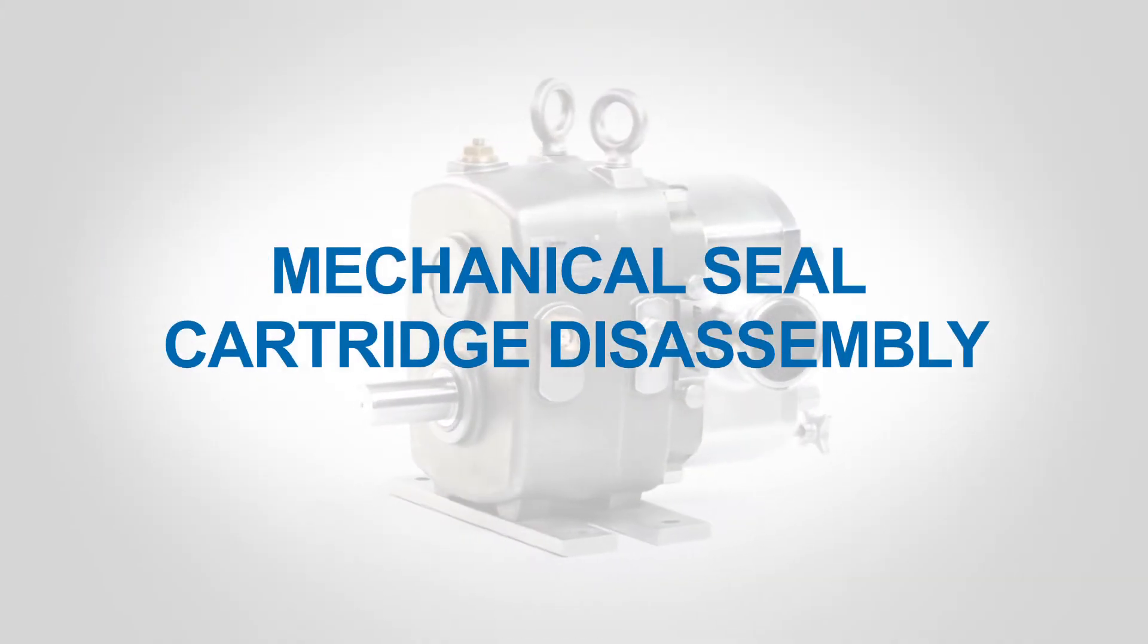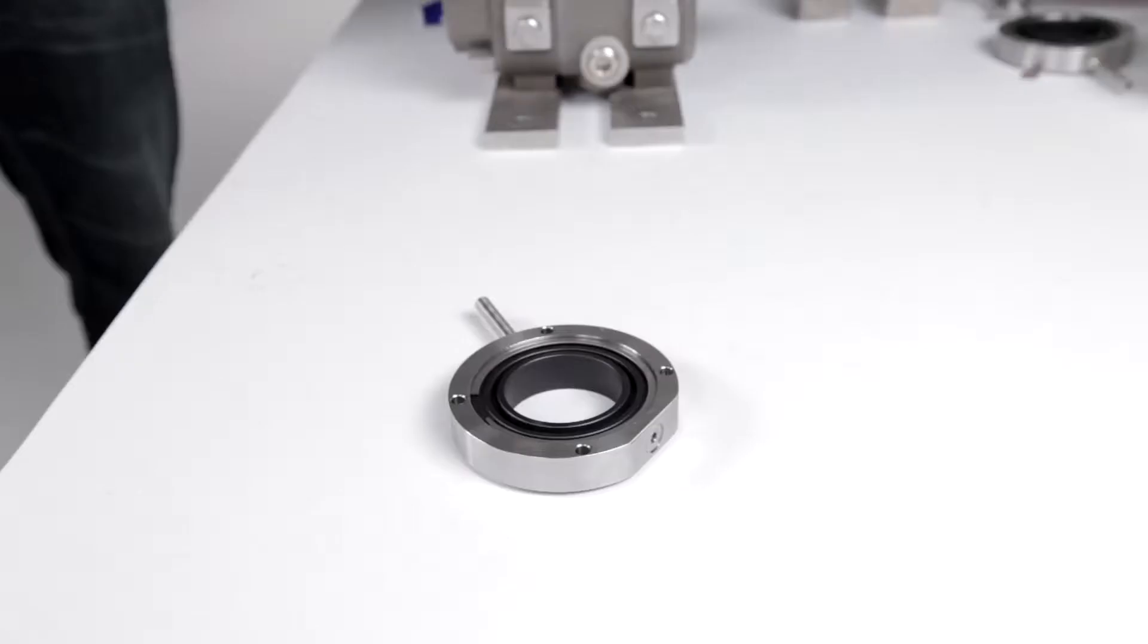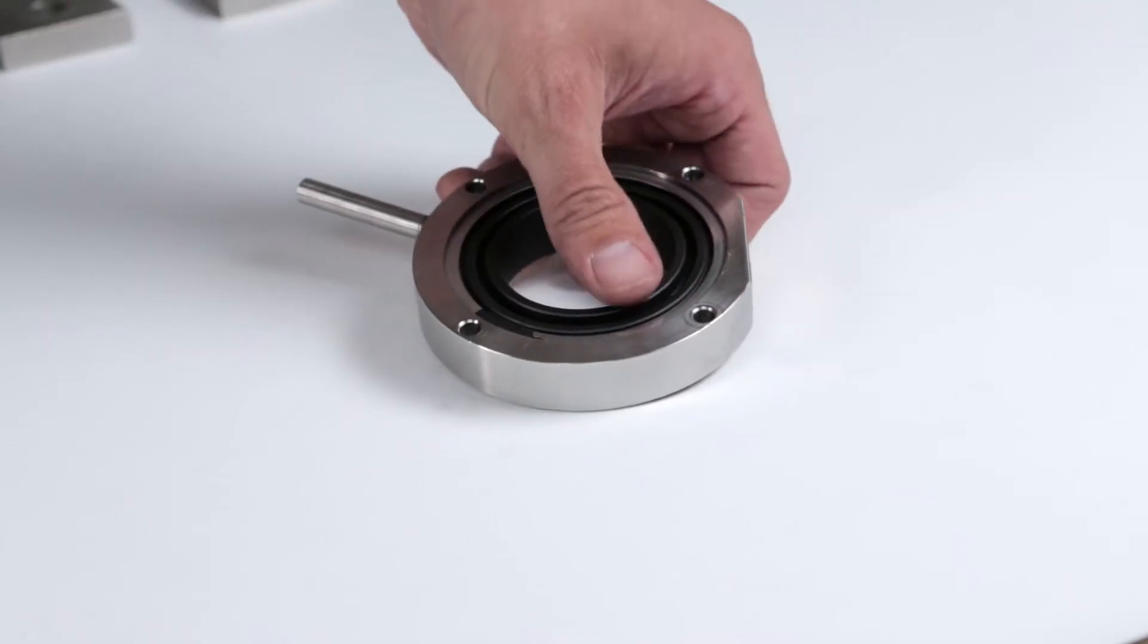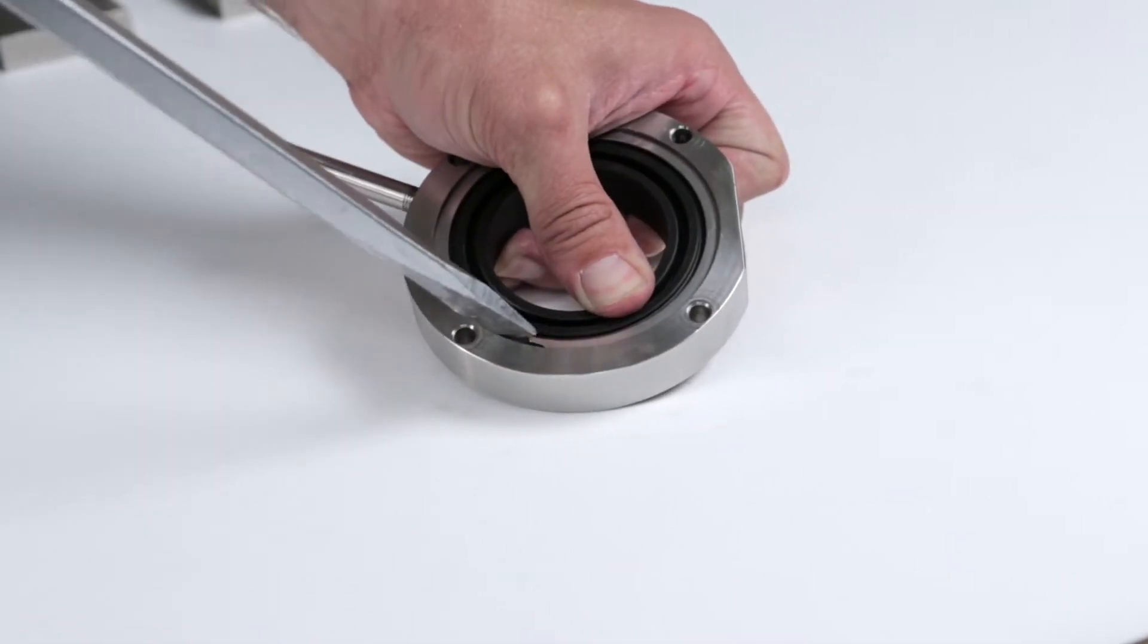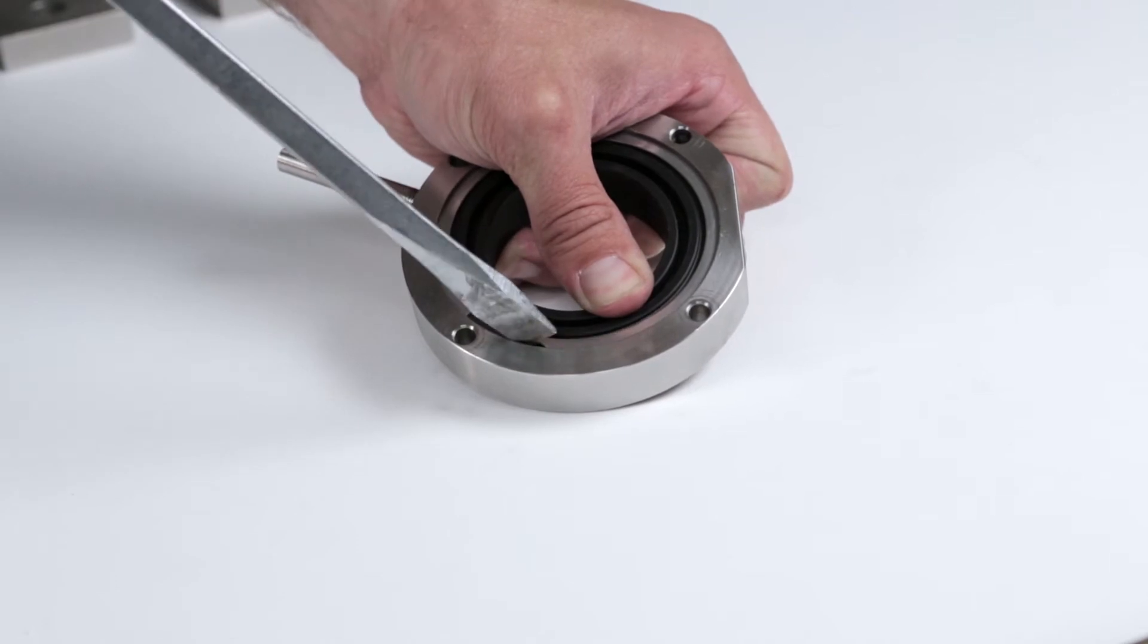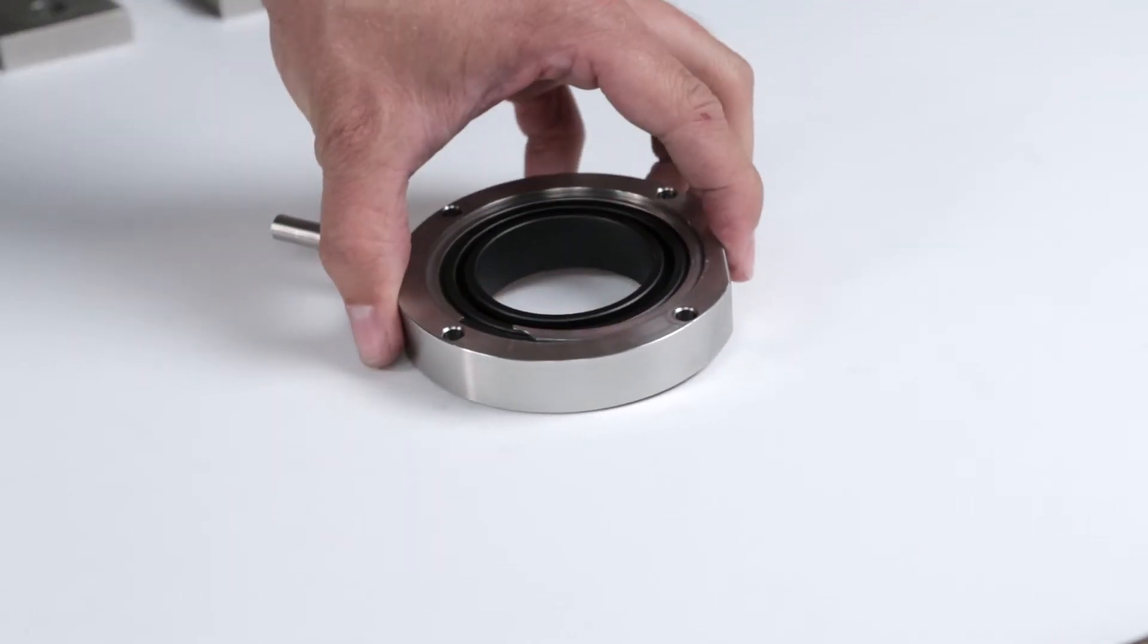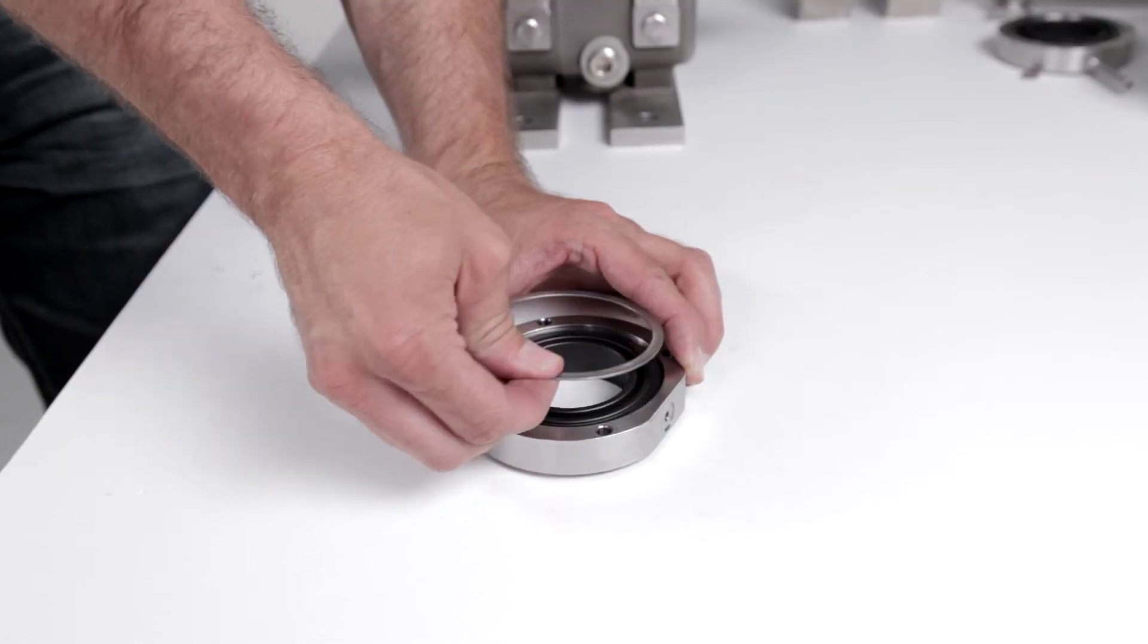Mechanical Seal Cartridge Disassembly. Place all of the seal parts on a clean work area and disassemble one cartridge at a time. Place the seal cartridge with the seal face up onto a flat surface. Compress the seal so that all of the pressure is off of the seal retaining ring. Pry the seal retaining ring out of the seal housing.